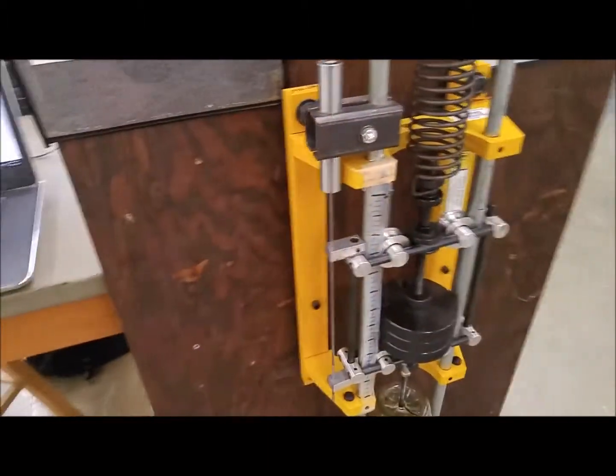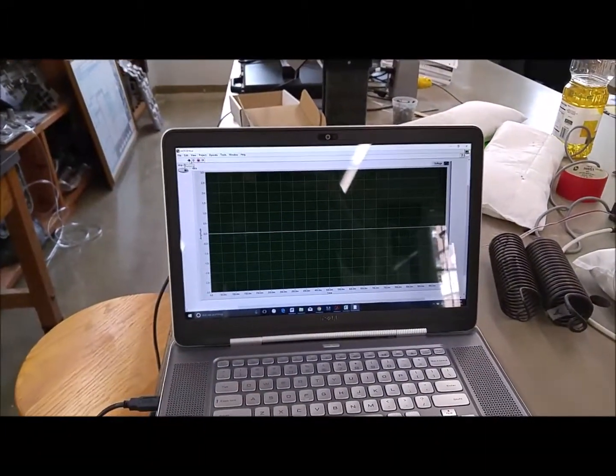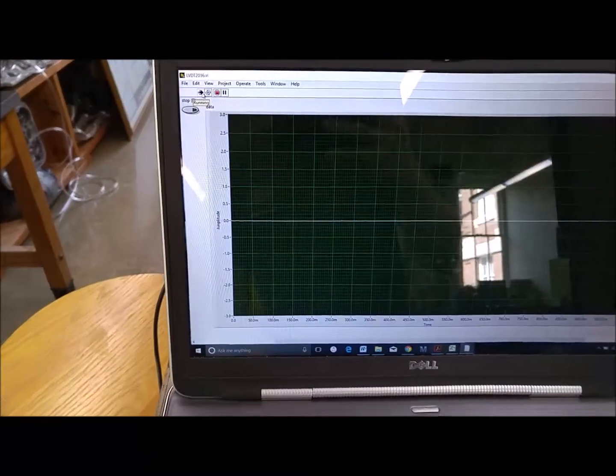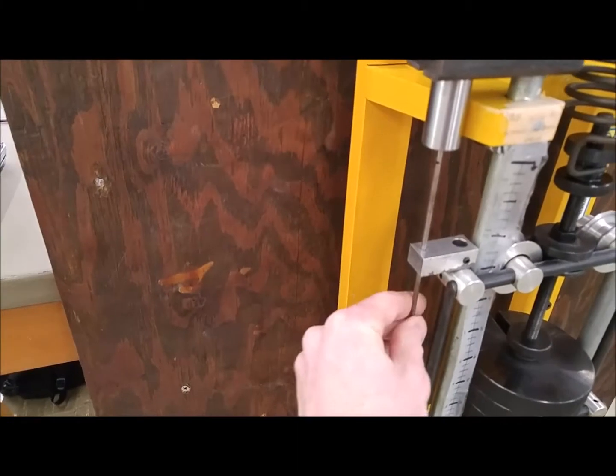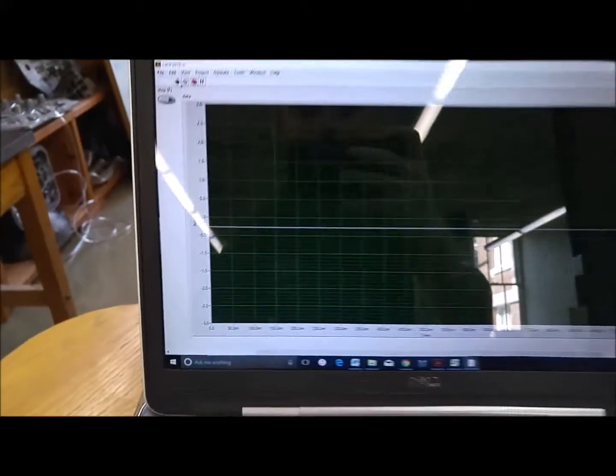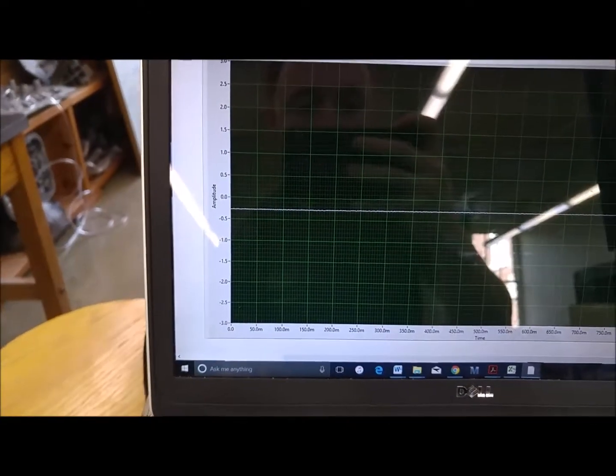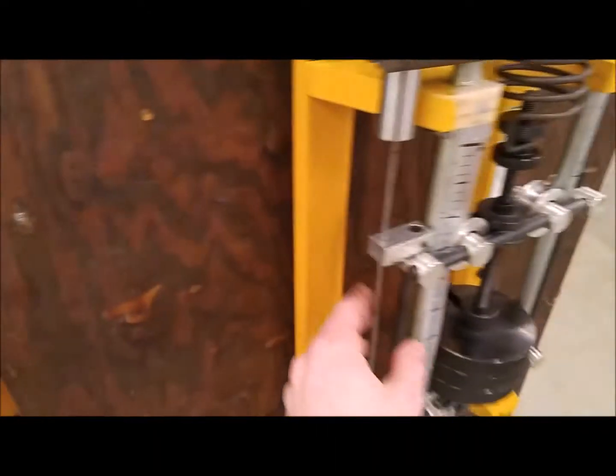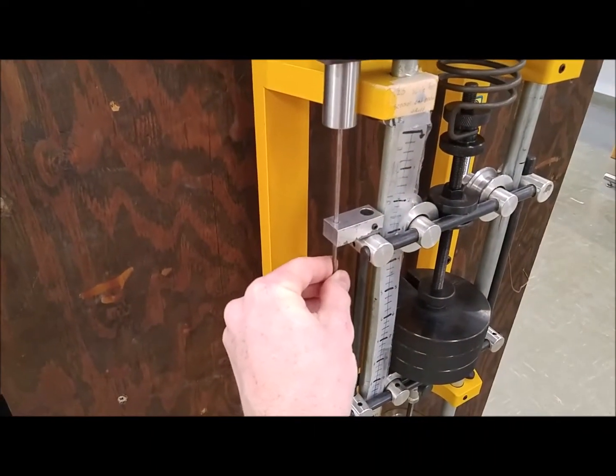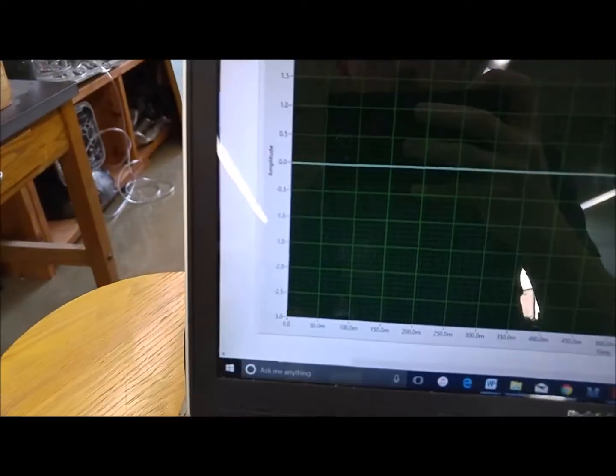So to do the calibration, basically we can look at the graph over here, and this is reading in real time. So we've got a voltage of 0 right now because I've already calibrated it. But if you hadn't had it calibrated, this is how you calibrate it, and you rotate it, that little piece. And now you can see we're a little below 0. So to get it back, I just rotate it back the opposite way. And now we're back at 0.